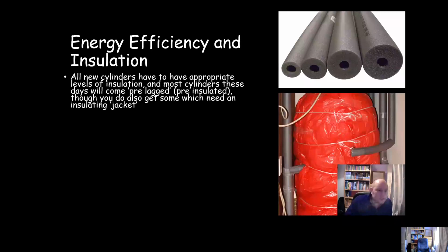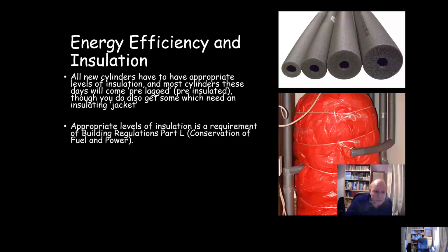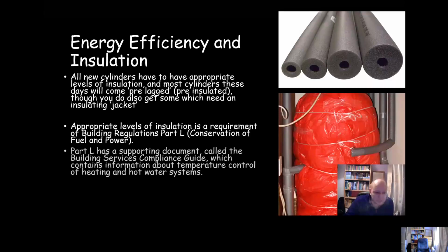Energy efficiency and insulation. All new cylinders have to have appropriate levels of insulation, and most cylinders these days will come pre-lagged or pre-insulated. Though you do still sometimes get some which need an insulating jacket. The requirement for insulation is set out in Building Regulations Part L, which covers conservation of fuel and power.